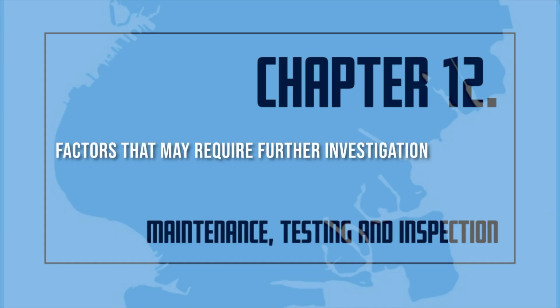Factors that may require further investigation. Installations that don't appear to be correct, including sprinkler heads located more than 22 inches below the ceiling or structure, sprinklers not installed in accordance with their listing, using sprinklers with a different RTI in the same protected area or the wrong RTI for the occupancy classification, undersized piping, incompatible piping materials, flexible sprinkler hoses not attached to the building structure, along with areas of the building not protected by the sprinkler system. All require further investigation by a qualified master fire suppression piping contractor.